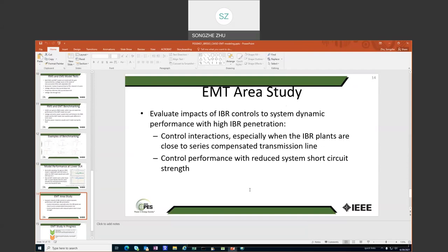So basically some oscillation between different plants, since they have different owners and are set up and tuned differently. When you put them together, they could oscillate against each other. Another focus area is to reduce the system strength and verify if we have a grid control problem.